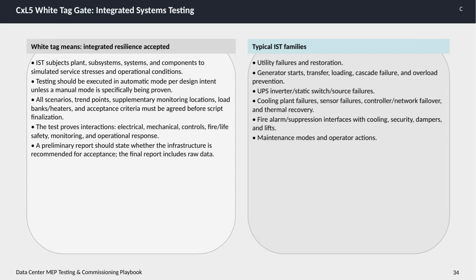Here we discuss the CxL5 White Tag Gate, which focuses on integrated systems testing, or IST. The term White Tag signifies that integrated resilience has been accepted, meaning the system's ability to withstand and recover from disruptions is confirmed. Integrated systems testing subjects the entire infrastructure, from individual plants and subsystems to complete systems and components, to simulated service stresses that mimic real operational conditions. It's crucial that these tests run in automatic mode, as intended by design, unless there's a specific need to validate manual control modes. Before finalizing the IST scripts, all scenarios, trend points, additional monitoring locations, tools like load banks or heaters, and acceptance criteria must be agreed upon. This ensures comprehensive coverage and clarity.